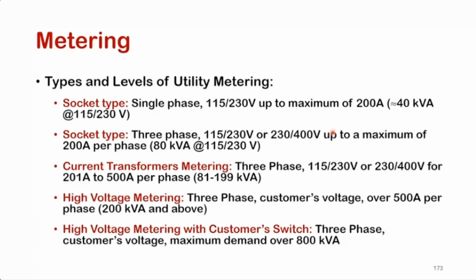The three phase now, it could go up to the 80 kVA, which is 200 amps per phase. So per phase, it could have 200 amps, right? But for higher voltages, you will have 201 amps to 500 amps. That's the maximum limit for CT metering, right? And then when you go up to high voltage metering, you have over 500 amps per phase, and then with high voltage metering the customer basically has their own switchgear and stuff like that in their facility to do their own switching, right?